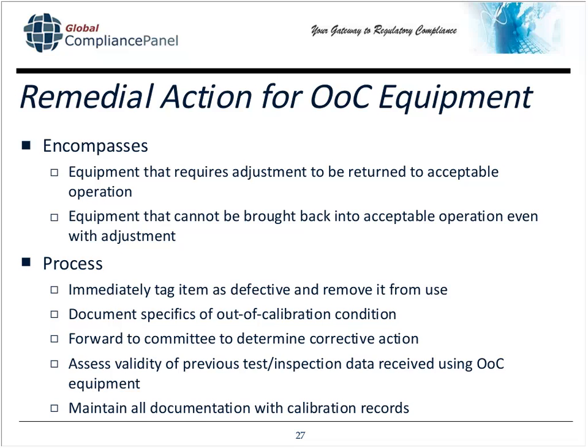Cross-functional teams that evaluate things like this are the best way to evaluate and recommend what corrective action should be taken. However, something you must do by regulation is to assess the validity of any previous test or inspection data or measurement data that you've received using this piece of equipment that was shown to be out of calibration, even though it was able to be adjusted to be brought back into calibration. The measurements may have been wrong.